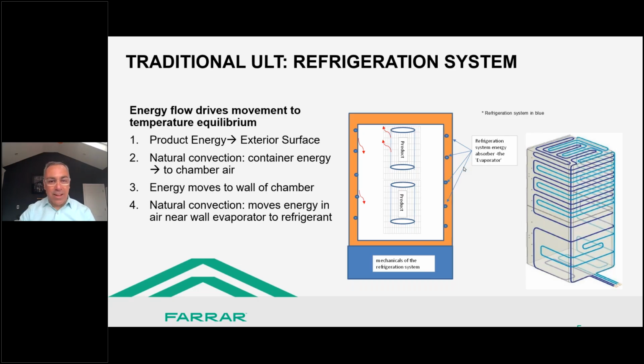In essence, this process relies on natural convection to move energy or heat from material and air within the chamber to the outside ambient. If you think about a space moving toward equilibrium, heat within the air and product moves outside the product, also known as the freezing process, and is represented by the red squiggly arrows here in this diagram. Natural convection moves the heat or energy towards the wall of the chamber, and the wall of the chamber is refrigerated. This is where the cold wall name comes from when we talk about cold wall ULT freezers. The wall of the chamber absorbs the heat, and natural convection also moves that energy or heat around to the wall evaporator to the refrigerant, which is pumped around the system and released as heat to the ambient.